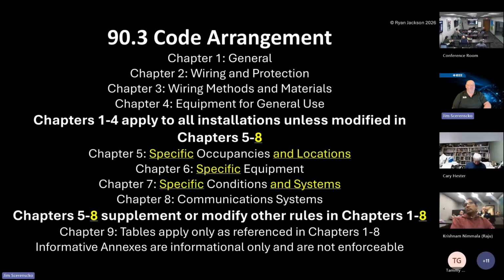So if one thing is called out in a chapter, like if it says you don't have to GFCI protect a sump pump if it's hardwired, but then you go back to 210.8 and 422 and it says all sump pumps shall be GFCI protected. Then you go to Chapter 6, Article 620 for elevators, and it says you shall not GFCI protect this if it's hardwired, because they don't want the pumps to stop running. And so that's how that works: this can modify what it says here. So this chapter says you don't do this, but then you go to this chapter and it says, hey, you have to do this, so it overrides. So 5, 6, 7, and 8 override anything that's in 1 through 4.